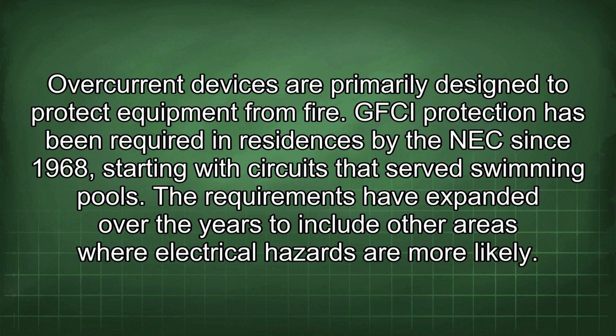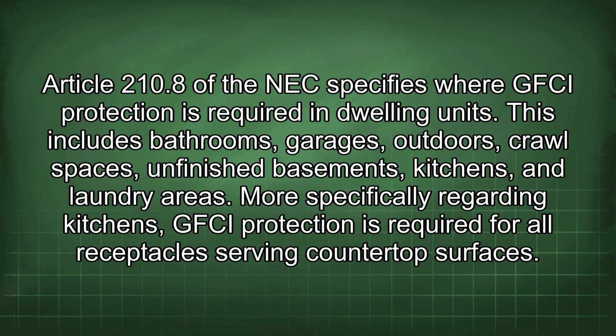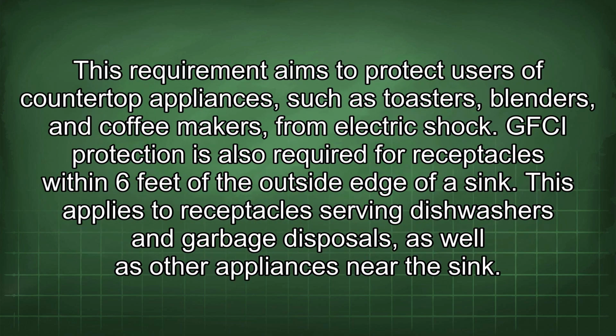GFCI protection has been required in residences by the NEC since 1968, starting with circuits that serve swimming pools. The requirements have expanded over the years to include other areas where electrical hazards are more likely. Article 210.8 of the NEC specifies where GFCI protection is required in dwelling units. This includes bathrooms, garages, outdoors, crawl spaces, unfinished basements, kitchens, and laundry areas. More specifically regarding kitchens, GFCI protection is required for all receptacles serving countertop surfaces. This requirement aims to protect users of countertop appliances such as toasters, blenders, and coffee makers from electric shock.